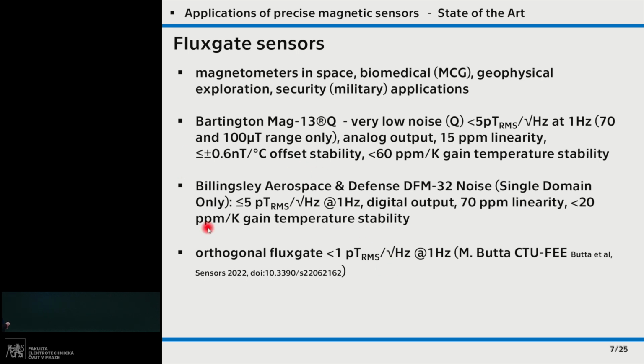There is another type of fluxgate sensor, the so-called orthogonal fluxgate, developed for example by Mattia Butta here at the faculty, which can reach sub-picotesla noise, but these sensors have some problems, for example with offset stability under some conditions. So parallel fluxgate sensors are still very useful for some applications, even though the noise is a little bit higher.